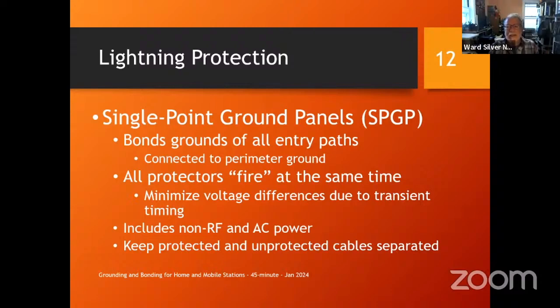And then that is connected to your perimeter ground. We're going to talk about perimeter grounds in a minute, but that's the grounding system outside the house that gives those heavy, direct paths into the earth. So your single point ground panel bonds all of the grounds together, and connects them to the ground system outside.